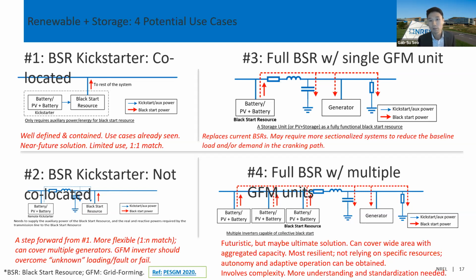The third case, shown top right, moves toward a more futuristic solution: a renewable-plus-storage unit acting as a full black start unit, replacing traditional black start resources entirely. As hinted earlier, operators may need to further sectionalize the grid given the size limitations of inverter-based black start units, since their capability would be limited compared to traditional resources. The inverter unit would need sufficient reserve, for example stored energy in a battery, to fully black start the system, which raises questions about economic merit, since it may limit the operating range of the storage unit.